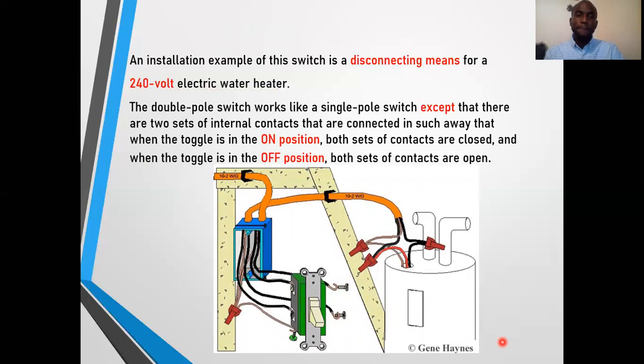Here we have a practical look at how this double-pole switch is used to control this water heater. I give credit to Mr. Haynes for creating this diagram. However, I had to make a slight adjustment to apply it to our color code. Because we use the Canadian color code, and many times when you look on the internet, you will see diagrams that have the American wiring code. So you will find out the differences in the wiring. I had to make a few adjustments to it. Here we have our double-pole switch, and as we can see, this would be our source wire coming from the breaker, and it now enters into this switch at the top.